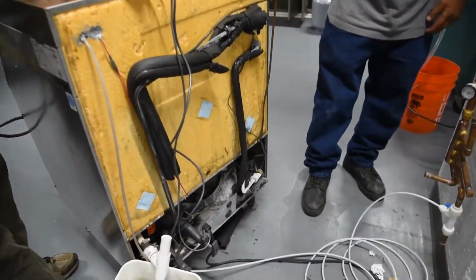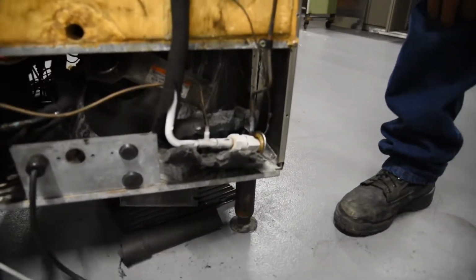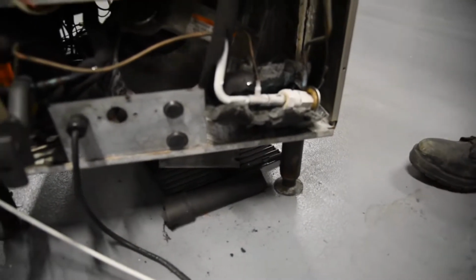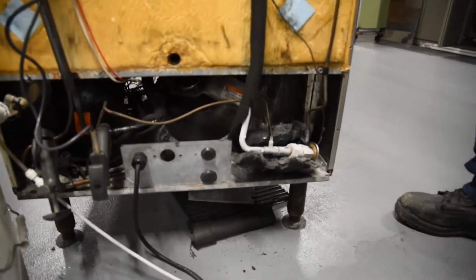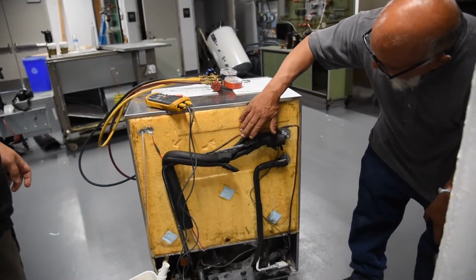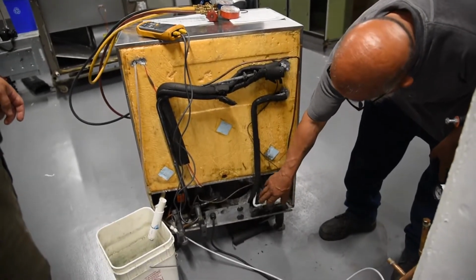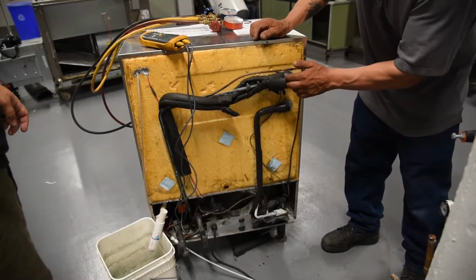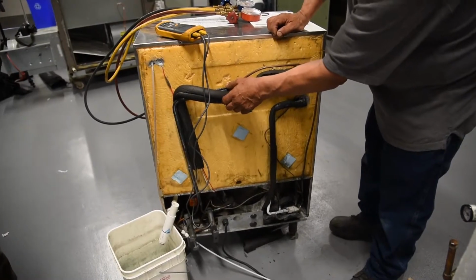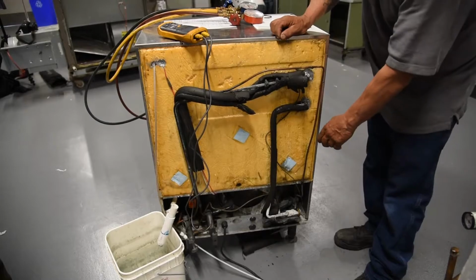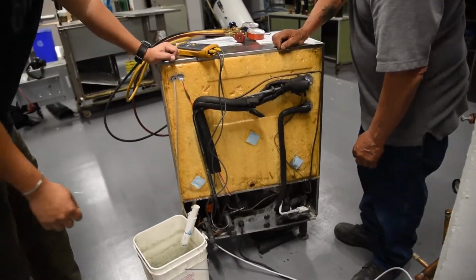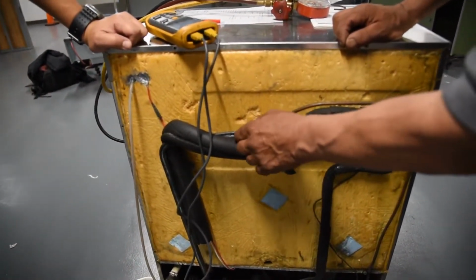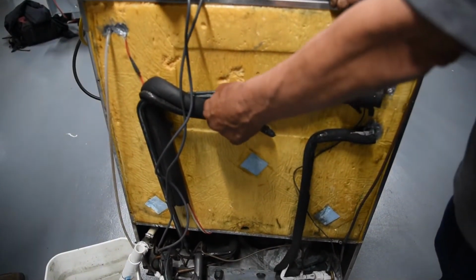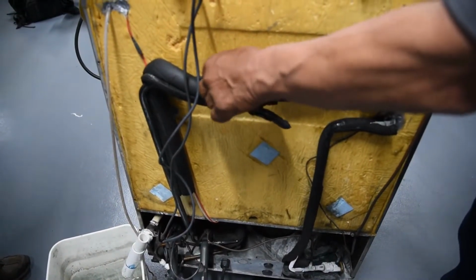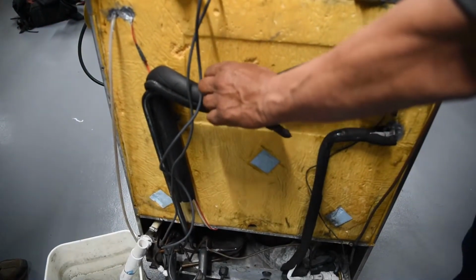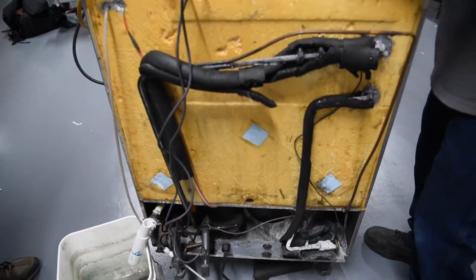Yeah. See how we're icing up on the TXV? Why are we icing up? Because it's below the freezing point, so the atmospheric moisture. Where's the ice coming from? From the ambient air. So now we have liquid coming into our TXV, going through the TXV, going into the evaporator, making ice, coming out of the evaporator, touching the liquid line, subcooling the liquid line to make it more operable with the TXV. So basically, this is a heat exchanger, right? What the suction line is doing is superheating because it's absorbing the heat out of the liquid. What the liquid is doing, it's subcooling because it's getting rid of the heat in the liquid. Okay.